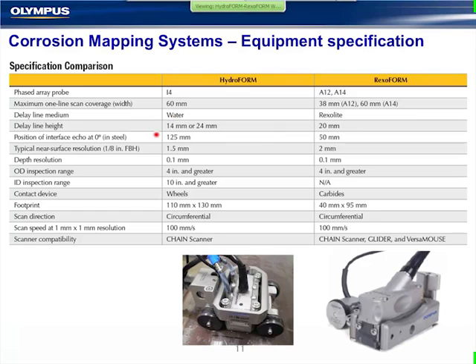The HydroFORM comes with two delay line adapters that allow us to adjust the height of the water column. This is necessary when you're inspecting components and the second interface echo is interfering in your area of interest in the data. So these were designed to put that second interface, just like an immersion tank 0-degree inspection, way out in time at 125 millimeters, and for the RexoFORM version of that, at 50 millimeters. Another way of looking at that is if I'm inspecting something less than 50 millimeters, I don't have to worry about the second interface echo interfering in my area of interest.